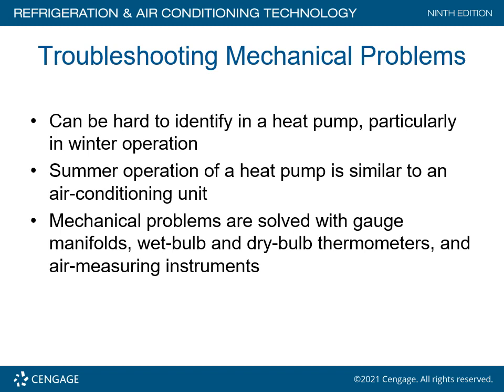It's really important you have ducting done correctly on heat pumps. Actually, it should be done correctly in any system, but heat pumps have a tendency to get a bad reputation because the installing contractor did not look at the ductwork issues prior to installing the equipment. If he did a bad job of identifying these airflow problems, you could have a very high-end heat pump system that's basically not going to work as designed, because the ducting did not take into account the issues that needed to be addressed, such as airflow into each room and return air going back to the main unit. So if the ductwork's not right, the heat pump's not going to work right. End of discussion.